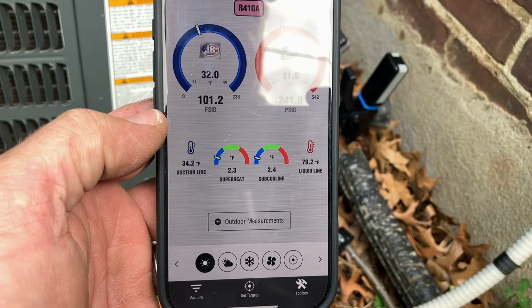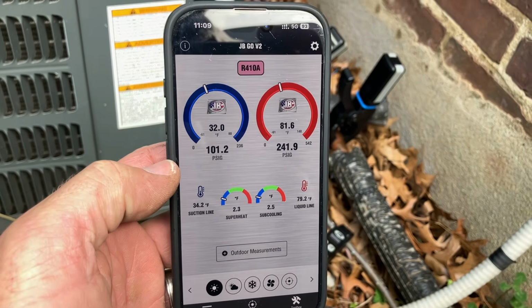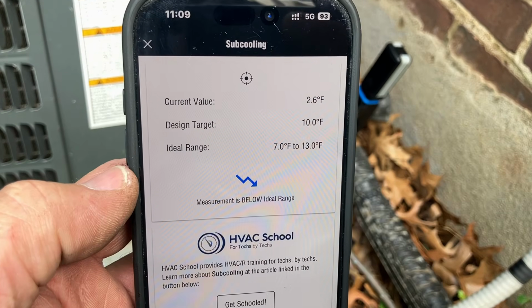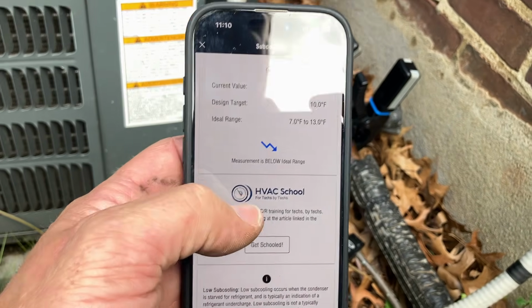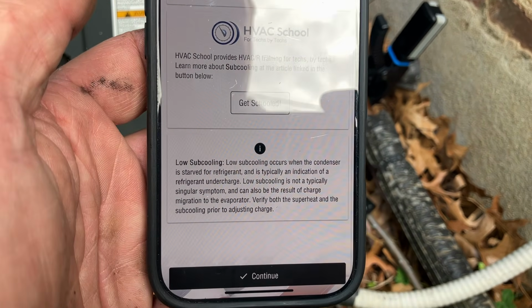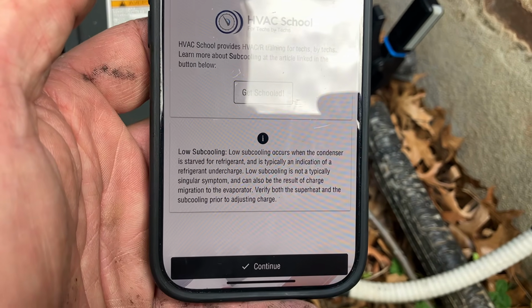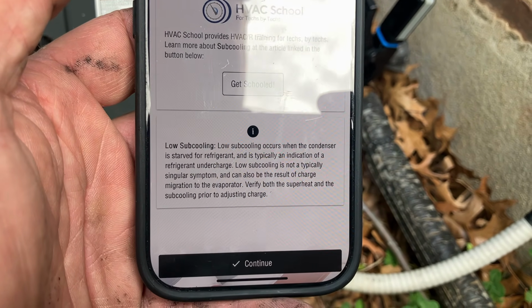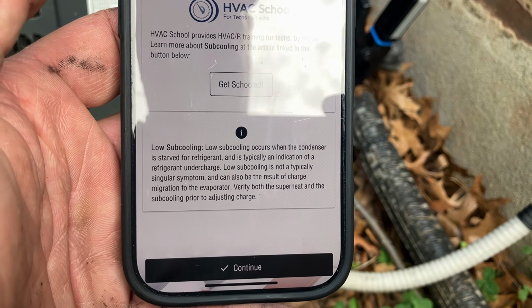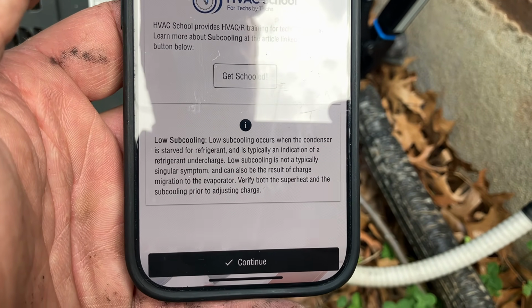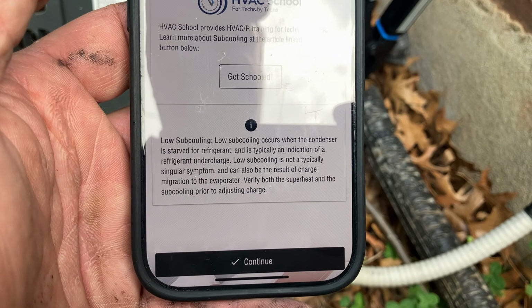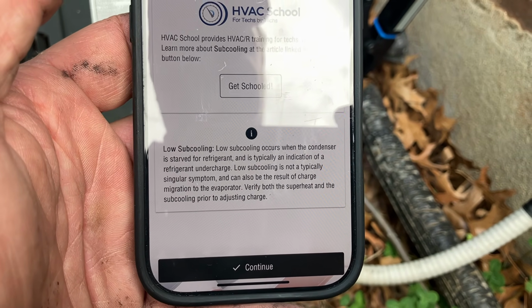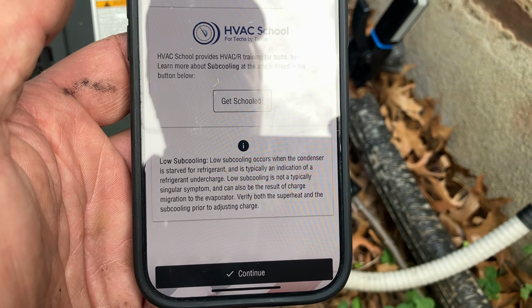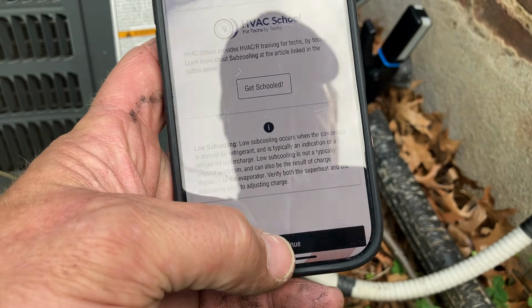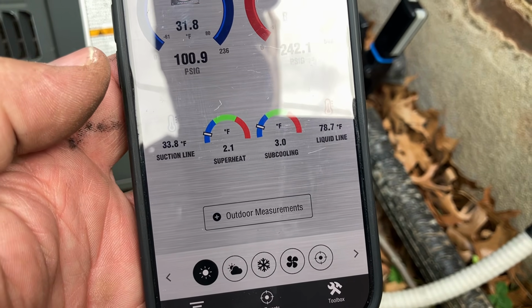Yep. I got TXV system with 2.5 degrees of subcooling. We undercharged. System is below ideal range. Low subcooling. Low subcooling occurs when the condenser is starved for refrigerant and is typically an indication of a refrigerant undercharge. Low subcooling is not typically a singular symptom. It can also be a result of a charge migration into the evaporator. Verify both superheat and subcooling prior to adjusting charge. Superheat is at 2.1 degrees, subcooling is at 3.